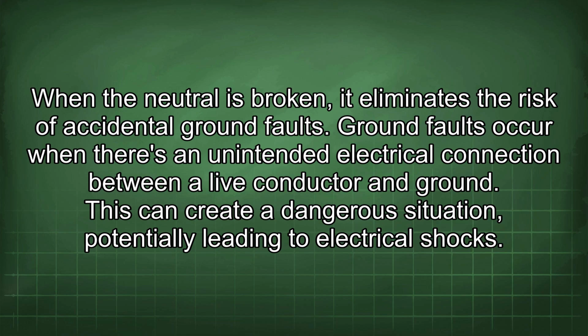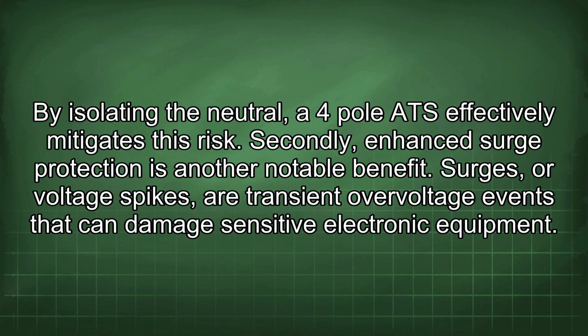Ground faults occur when there's an unintended electrical connection between a live conductor and ground. This can create a dangerous situation, potentially leading to electrical shocks. By isolating the neutral, a 4-pole ATS effectively mitigates this risk. Secondly, enhanced surge protection is another notable benefit.